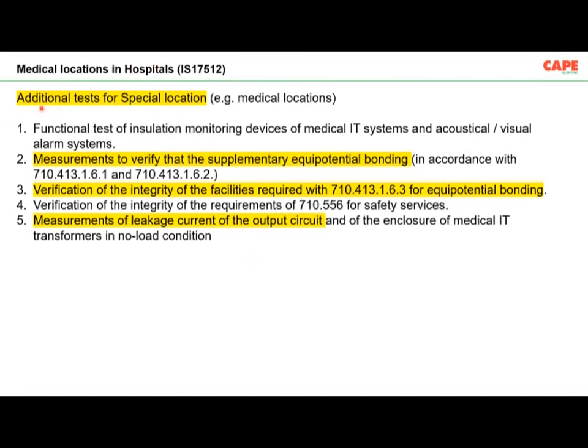Similarly, in a hospital, additional test for special location. What is a special location in a hospital? Special location is, for example, an operation theater or an ICU or the locations where class 1, class 2 medical equipments are used. The class 1, class 2 medical locations are there. So for those cases, number two, measurement to verify the supplementary equipotential bonding. What is supplementary equipotential bonding? Imagine you have an operation theater. All the metallic items in that particular operation theater must be interconnected in such a way that during normal condition, the touch voltage between two simultaneously accessible parts is less than a certain millivolt, maybe 30, 40 millivolt. So you need to have a very good connection.